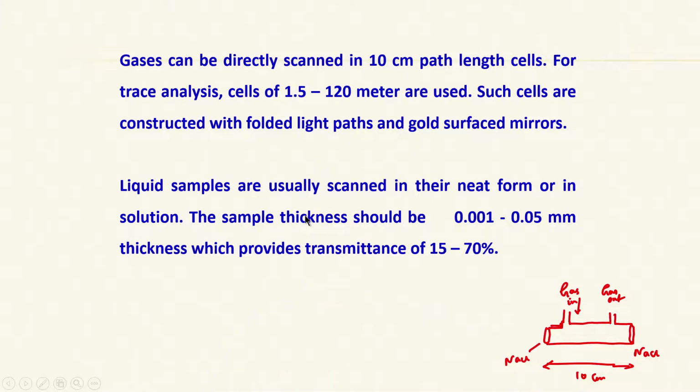If it is a normal laboratory gas analysis, you use a 10 centimeter cell like what I have shown you in my previous slide. That is very simple. So, this is the kind of gas cell. Then how do you do liquid samples?